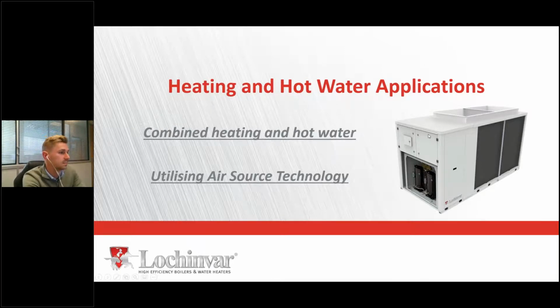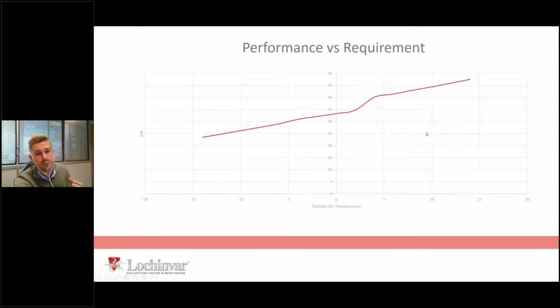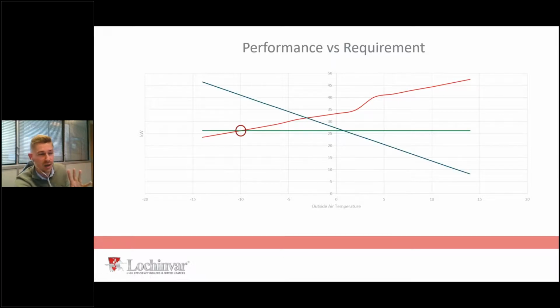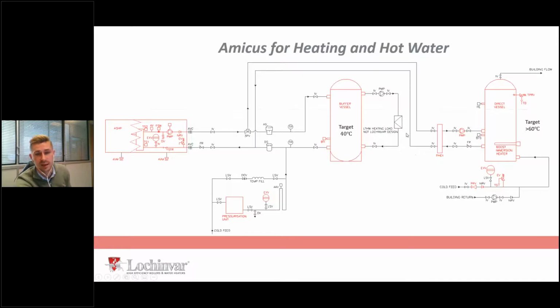So that's hot water. And now, just to prove electric air source heat pumps' versatility, I'm going to show you one last schematic. This is an amalgamation of the previous 2 charts, so I'm not going to labor it too much. But let's just look at a heat pump doing heating and hot water. So, air source heat pump, thermal store for heating, domestic hot water vessel. The air source heat pump should be supplied with 2 sensors, your heating sensor and your hot water sensor, so the BTS, sanitary hot water sensor. That gives you the ability to have 2 different target temperature zones.